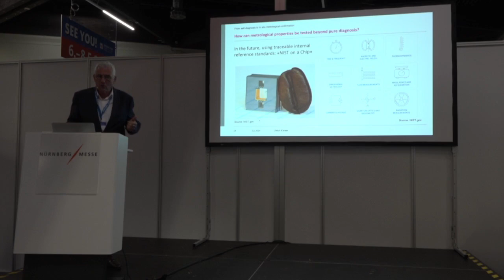When you have a measurement device, you have certain components. You have maybe a primary sensor, then you have a clock, then you have an amplifier, then you have a voltage, and at the end you get the result. And my idea, our idea, is not to test the entire system, but maybe some components which are accessible, you measure and check against references. Not 100%, but a few of them. And this I have written here: components, not all, but many, that contribute to metrological quality must be tested against internal references. And this I name metrological testing.